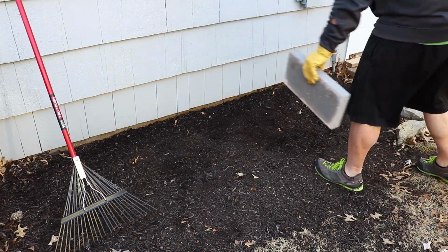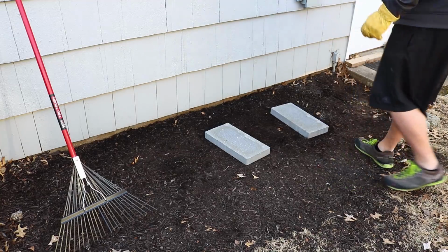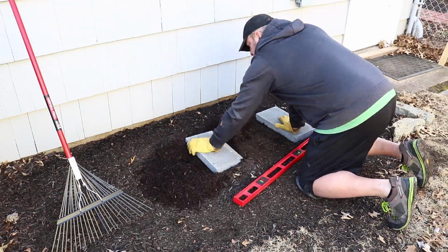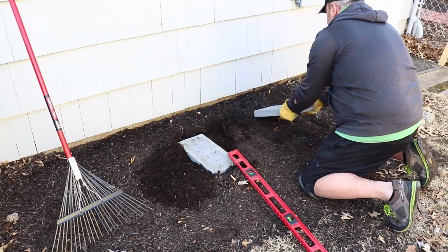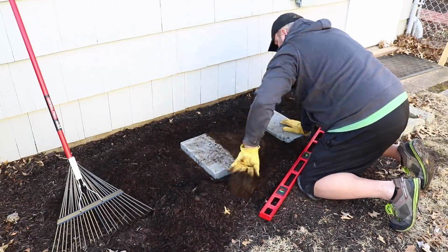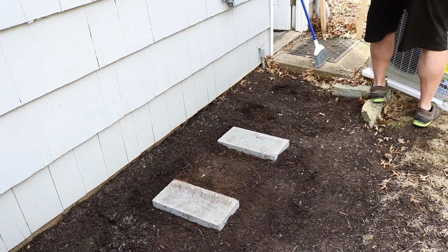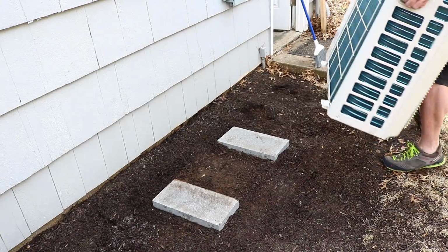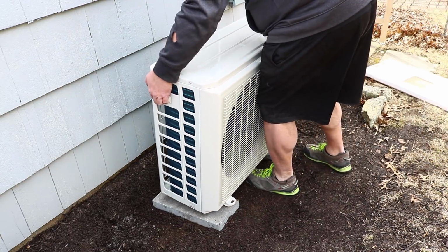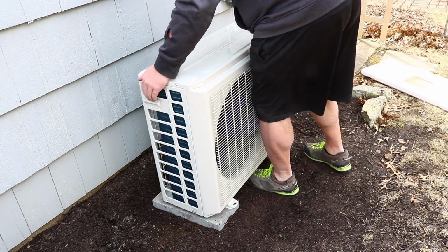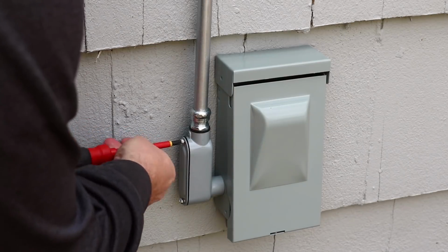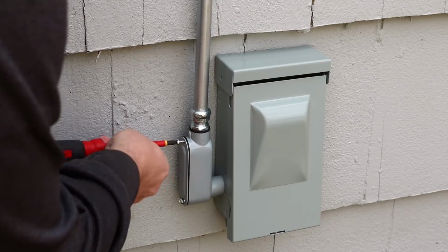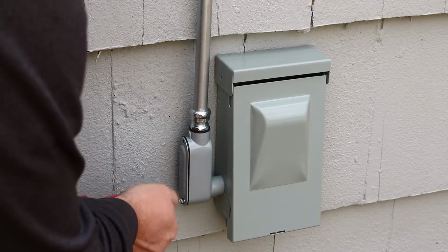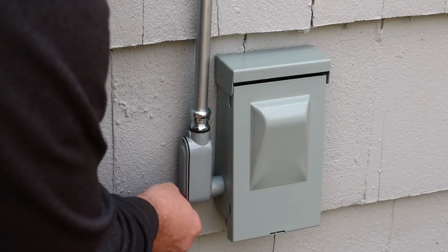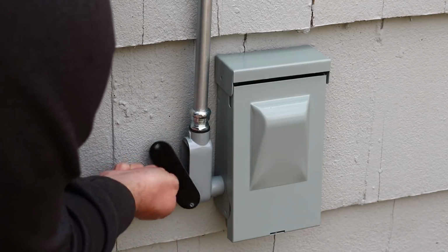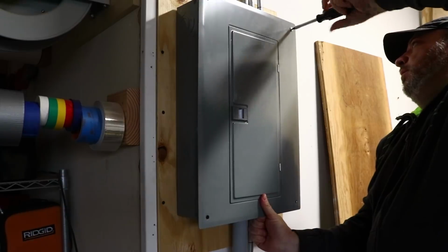I now needed to prep the site for the outdoor unit. I placed these on a couple of concrete pavers, and the most important thing here is to make sure that both of these pavers are perfectly level. I could now go ahead and place the outdoor unit down onto the pavers. I now needed to get power from the panel to the disconnect box, so I started out by removing the cover from one of these L's, and then went inside and took off the cover to the sub panel.